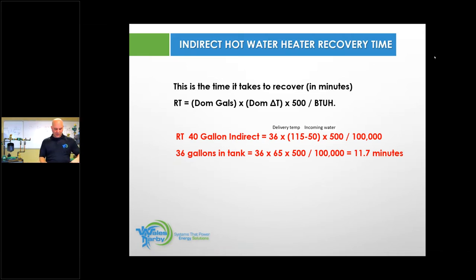So this is where we're going to start to do some work. I said a lot in week 3 and week 4, but we're going to do a little bit today also. So write this down. It's the same indirect. It's 36 gallons. In your parentheses this time, I want to elevate the 115. I want to make that 120. The incoming water will remain at 50 degrees, but somebody put a Honeywell zone valve on this indirect. So that means our 100,000 BTU boiler goes away and you replace that with 35,000 BTU.